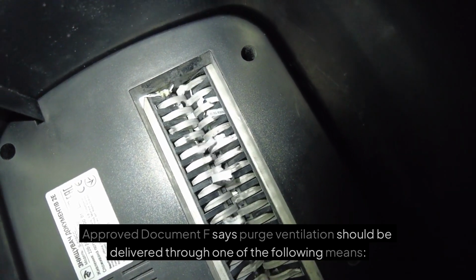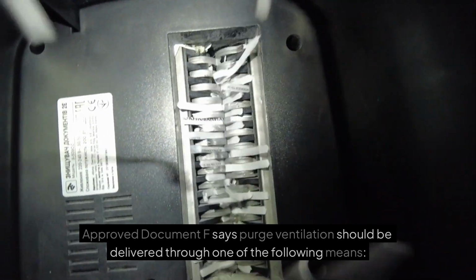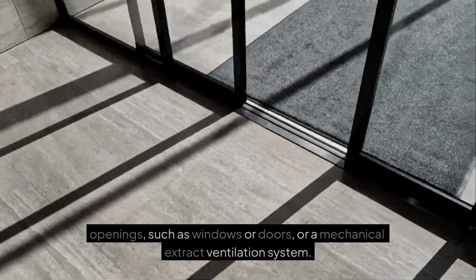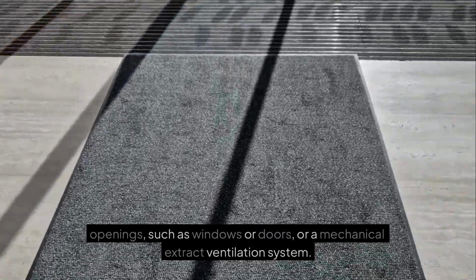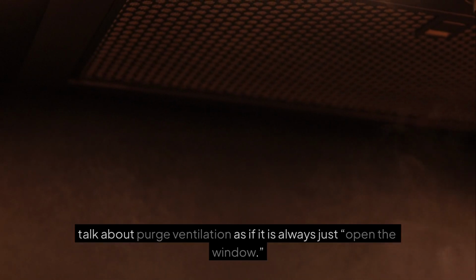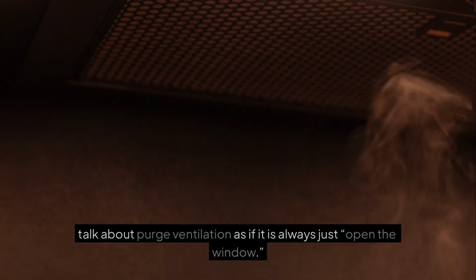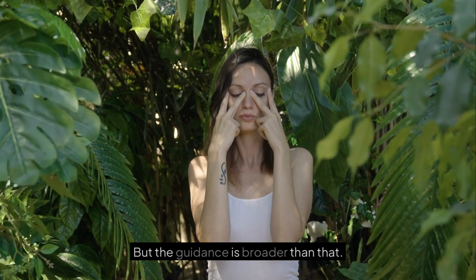Approved Document F says purge ventilation should be delivered through one of the following means: openings, such as windows or doors, or a mechanical extract ventilation system. That is really important because some people casually talk about purge ventilation as if it is always just open the window. But the guidance is broader than that.